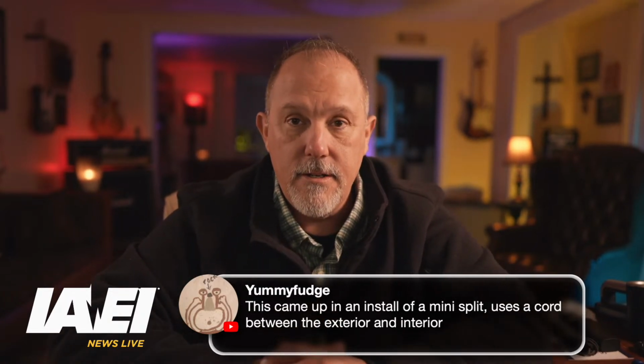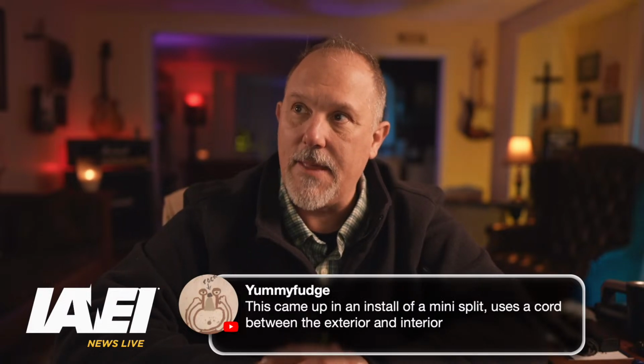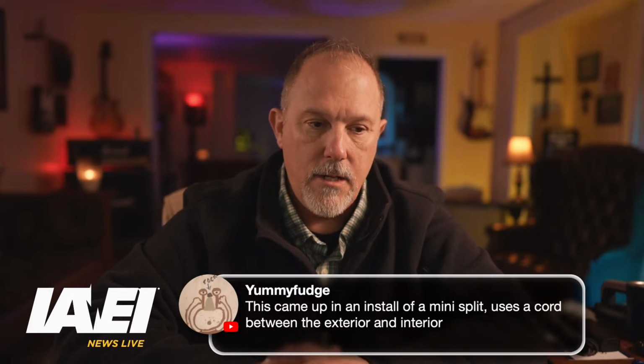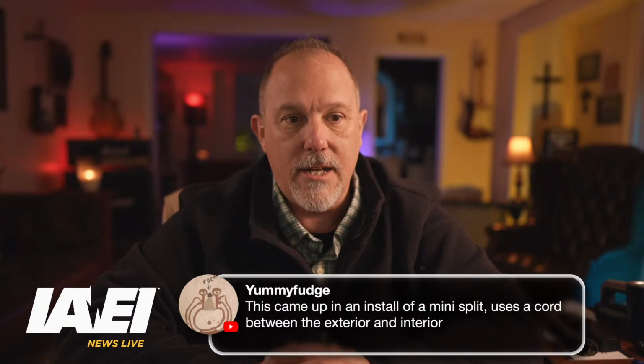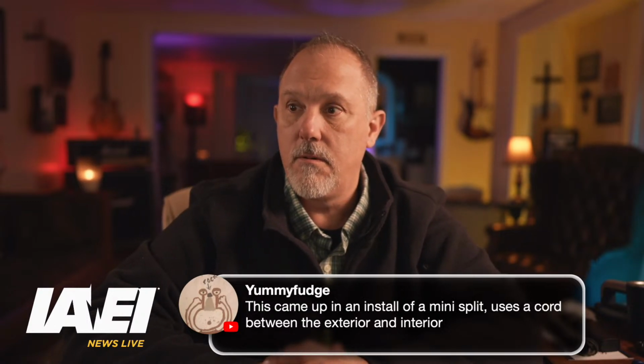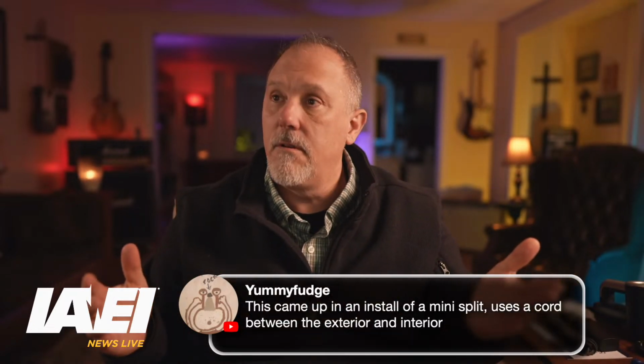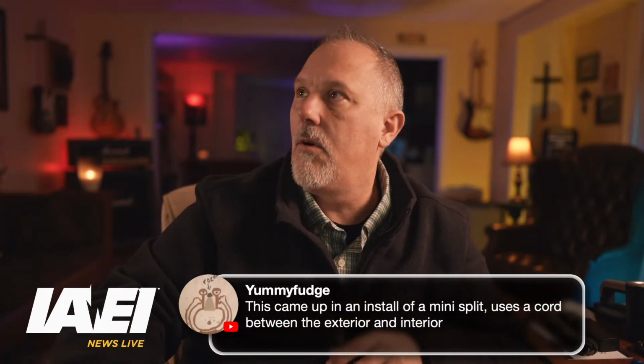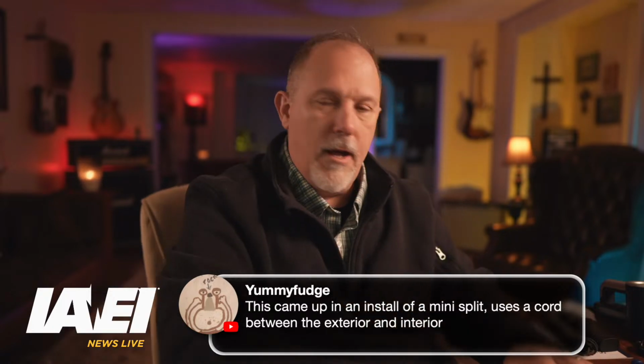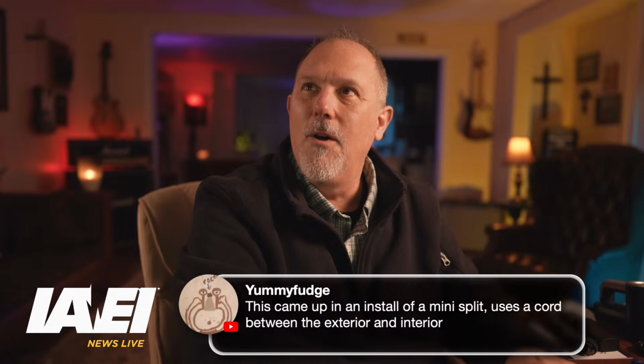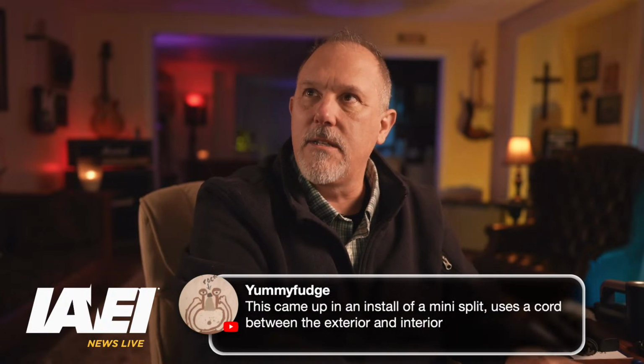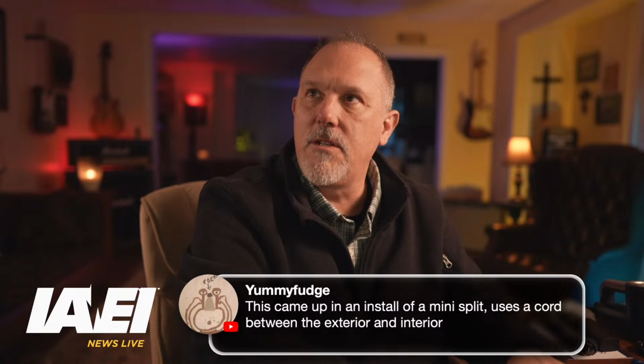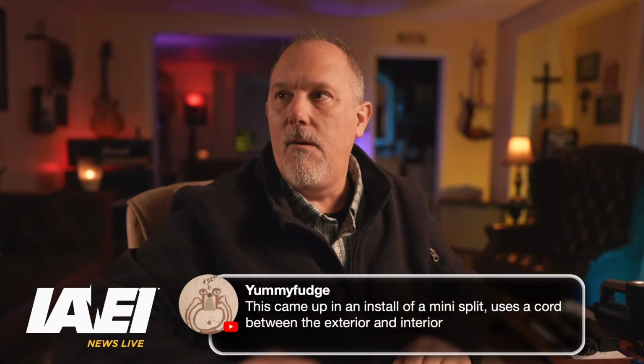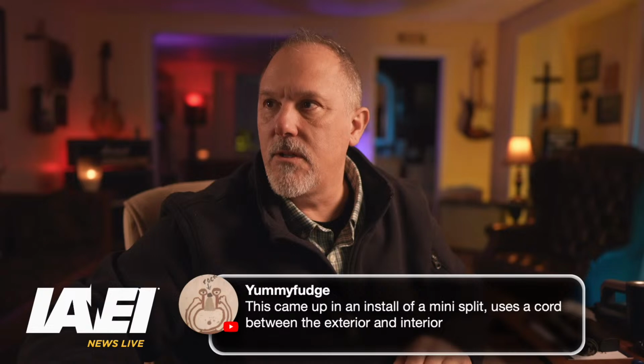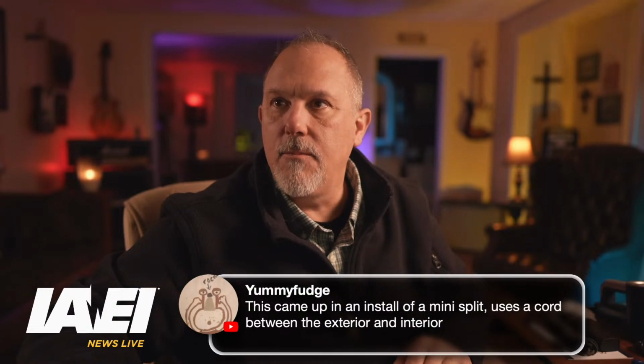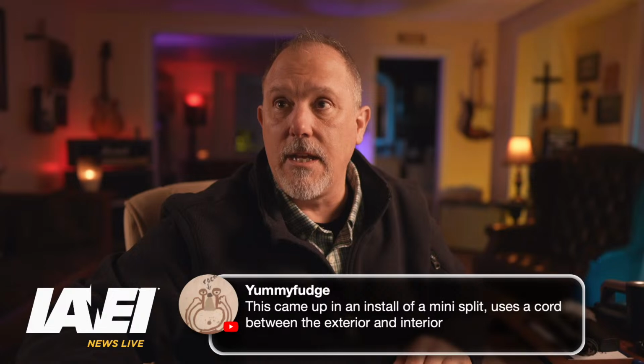Mr. Hofkin, UL, what does UL have to say about that conductor that goes between in a mini split application? Is that a flexible cord? Is it not a flexible cord? The conductor between units, the connecting cables, connects to the indoor and outdoor units.